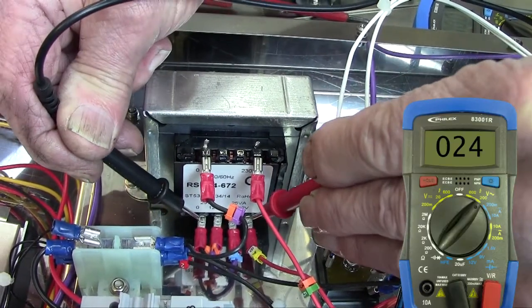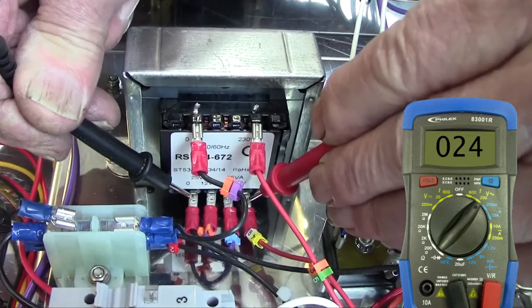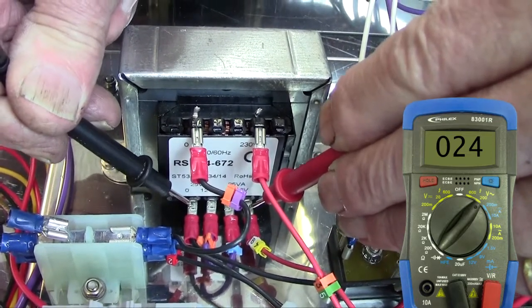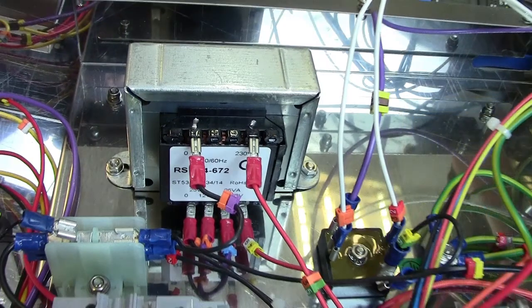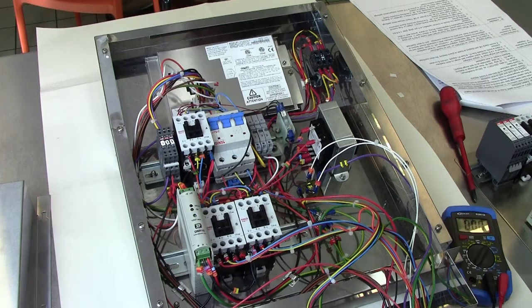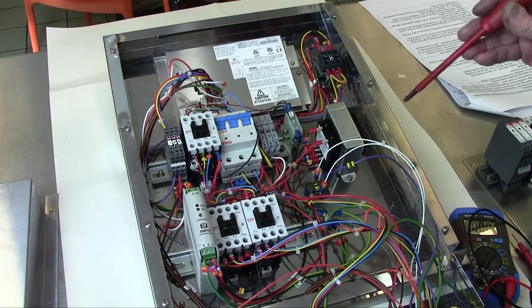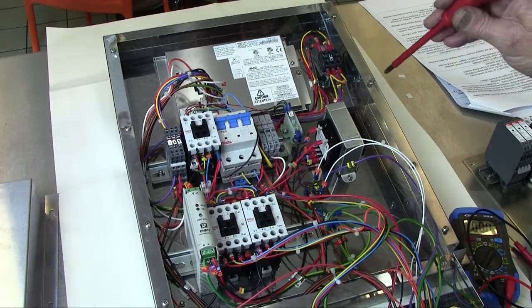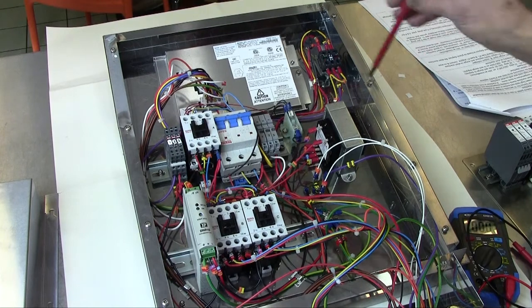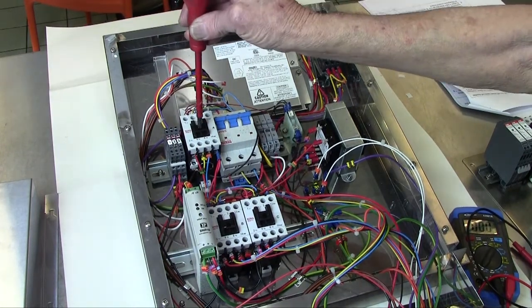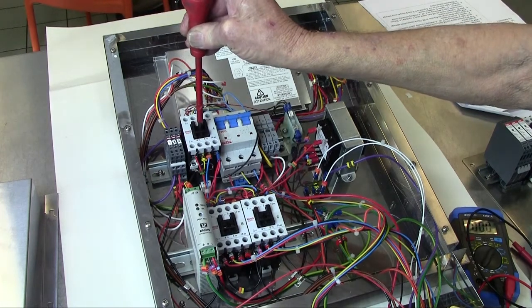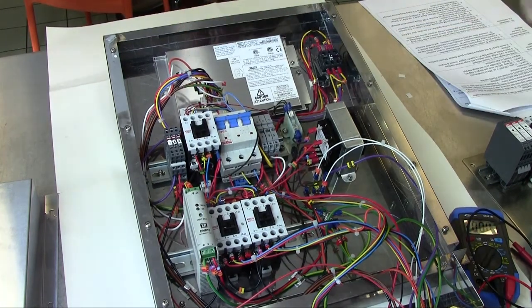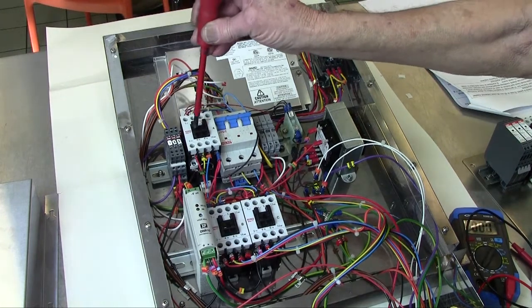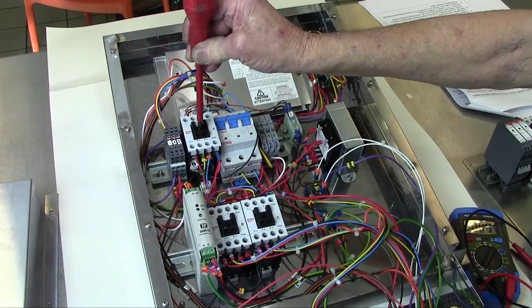And if that checks OK, check the output, which is the two extremes on the bottom, and that should read 24 to 30 volts. They're both AC. If the bottom doesn't read, replace the transformer. If the transformer checks out OK and doesn't require replacing, a quick check is to use an insulated screwdriver and press a contactor in, and if it latches, continue with the checks. If the contactor doesn't latch, replace the contactor.